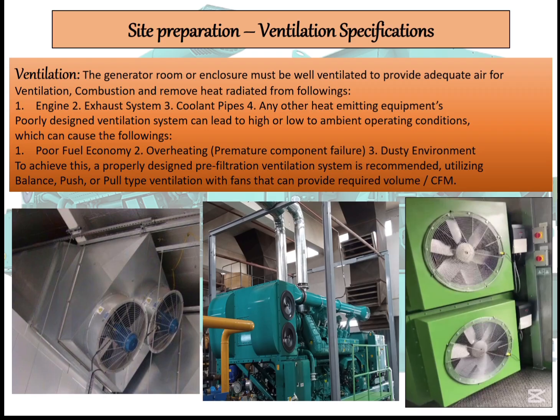We can achieve this ventilation system with three different methods. Number one is balanced ventilation. On one side of the powerhouse, at the inflow, we are sucking fresh air from outside the powerhouse or enclosure. On the other side, we have extractor fans that push the hot air out into the atmosphere.